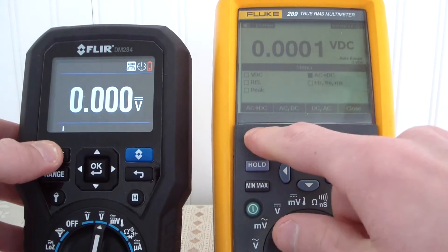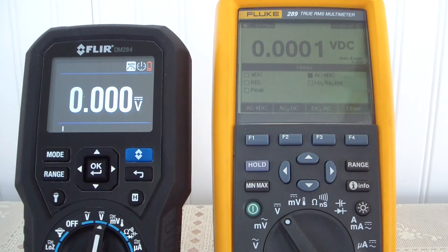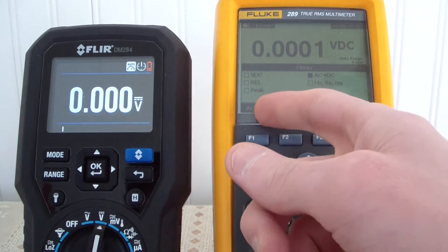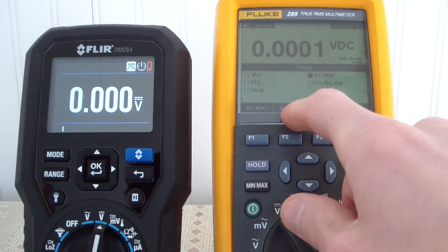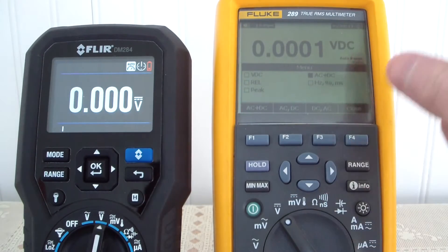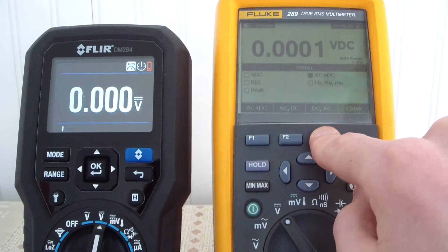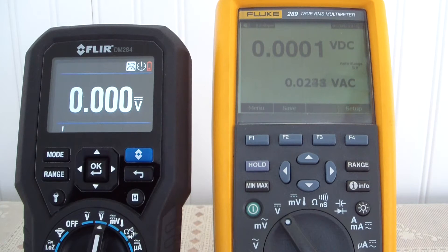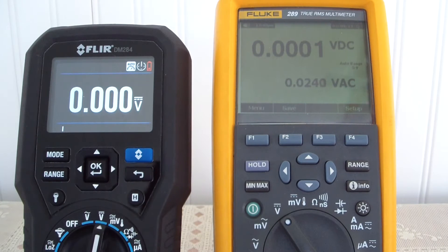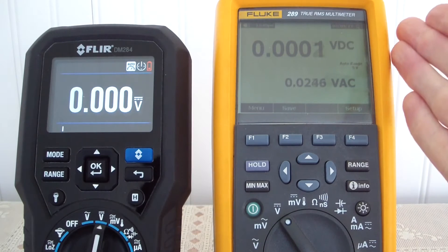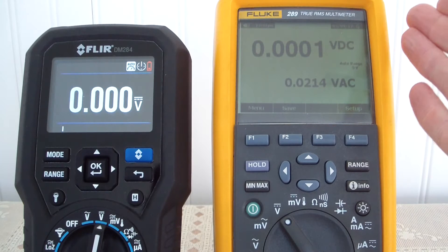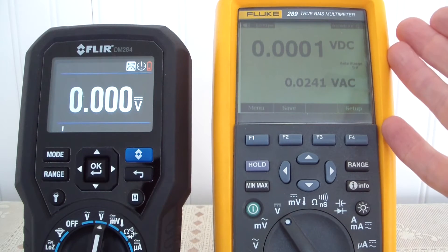Now this is a really cool feature on the Fluke that I've only used once: you have the ability to combine AC and DC simultaneously — AC on the top and DC on the bottom, or DC on the top and AC on the bottom. It's a really cool function if you're not exactly sure what your source is.